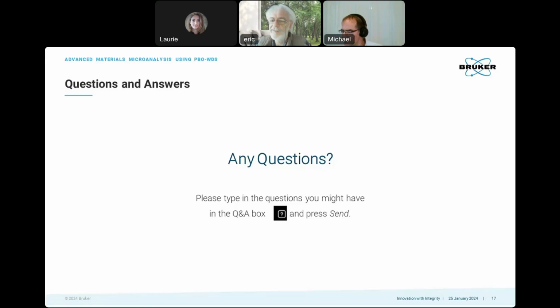No worries. There was a question about the timing to get enough counts for resolving light elements in WDS against EDS. Of course, the timing to get enough counts is not the same by WDS compared to EDS. EDS is very fast, and especially if you work at high beam current, like 5 nanoamps, with EDS you can get a spectrum very rapidly. So it is not the problem here.